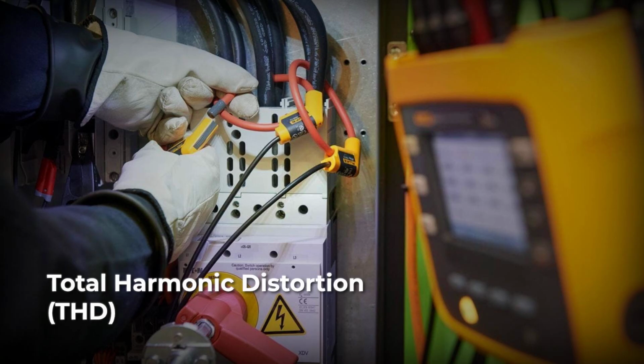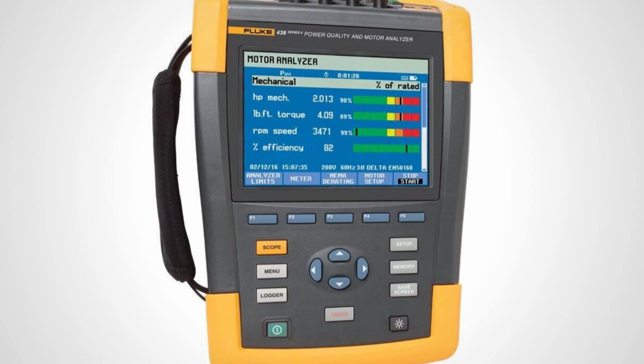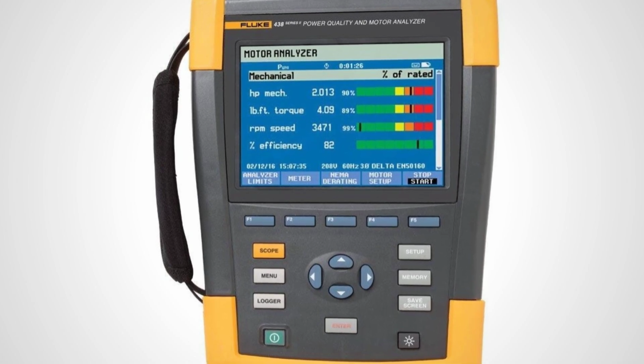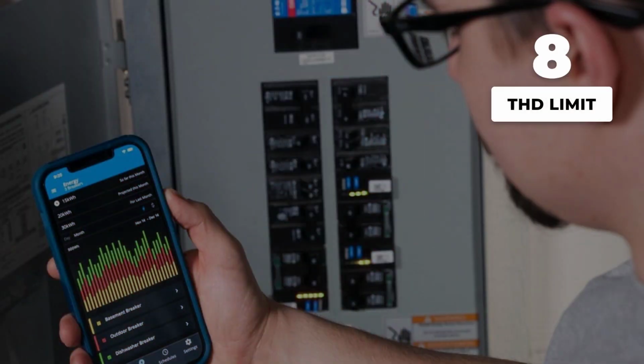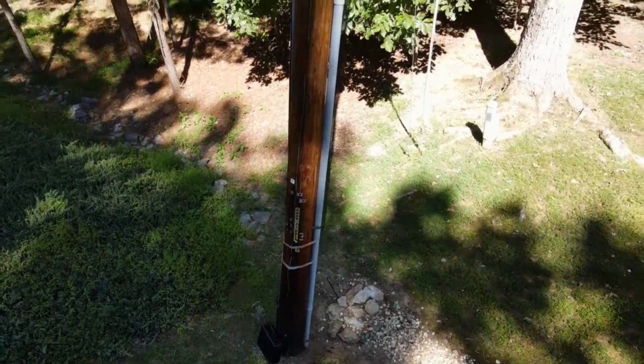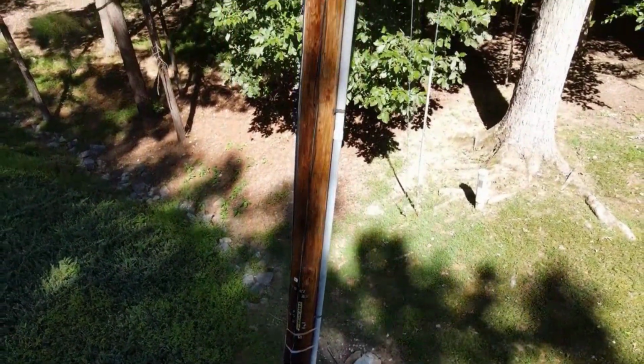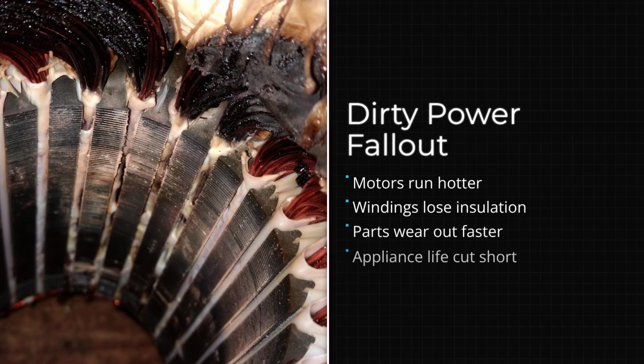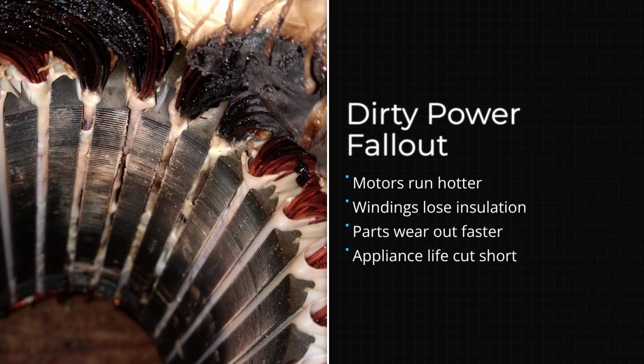Engineers track this with total harmonic distortion, or THD. In theory, THD should be 0. The IEEE 519 standard sets the red line at 8% for low voltage systems. Cross that, and the grid's harmony is broken. Motors overheat, windings degrade, and the lifespan of devices shrinks.